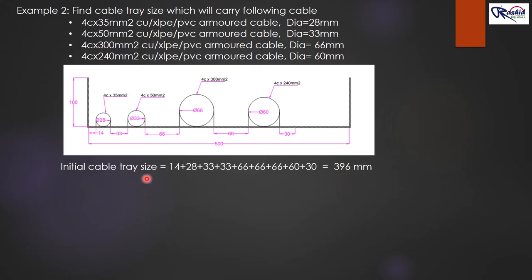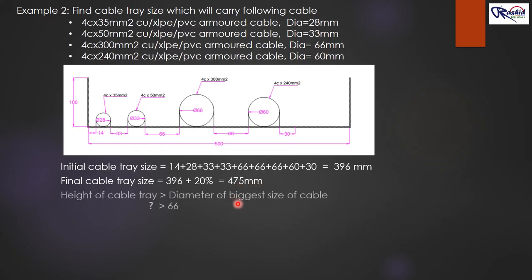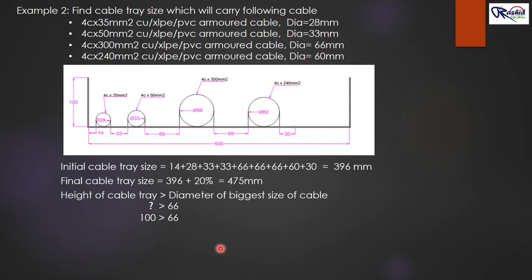These are the initial values. We need to add 20 percent extra for the final cable tray size. After adding 20 percent, it becomes 475 mm. Since 475 mm is not a standard market width, we select the next higher available size, which is 500 mm. For the height, the formula is the same: height must be greater than the diameter of the biggest cable, which is 66 mm. The next available size greater than 66 mm is 100 mm. Therefore the final selection is a 500 × 100 mm cable tray.